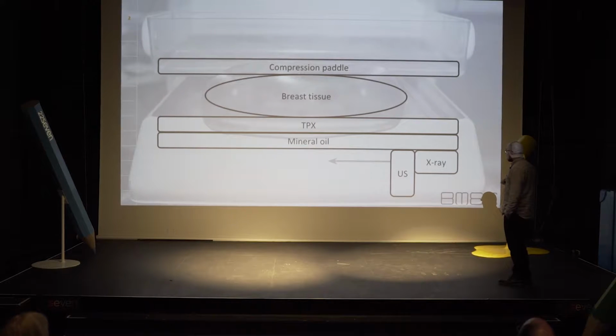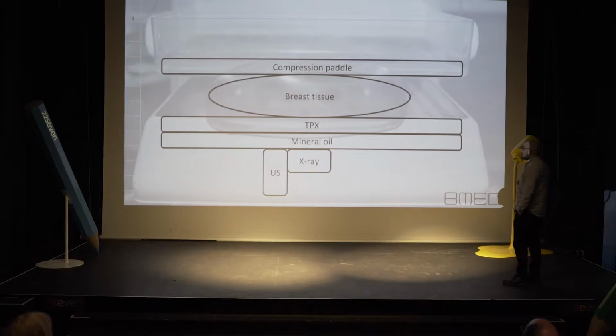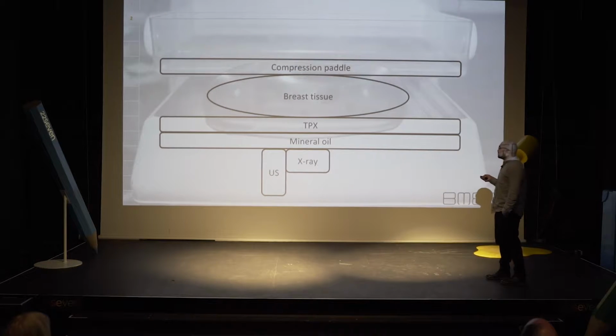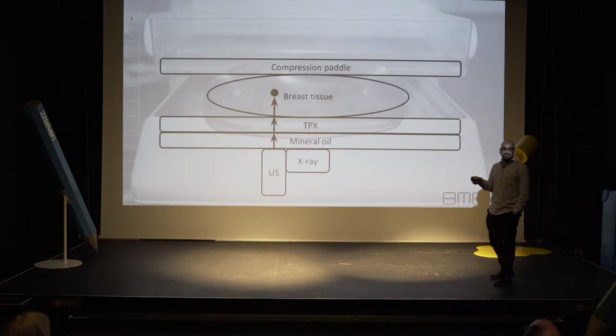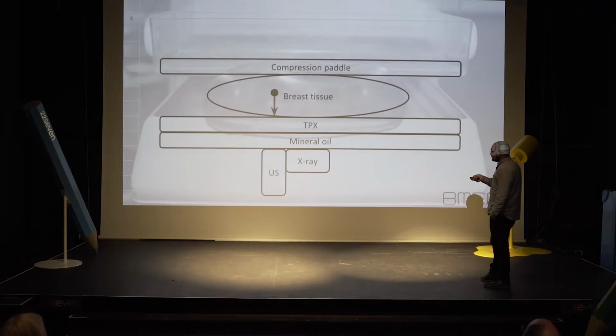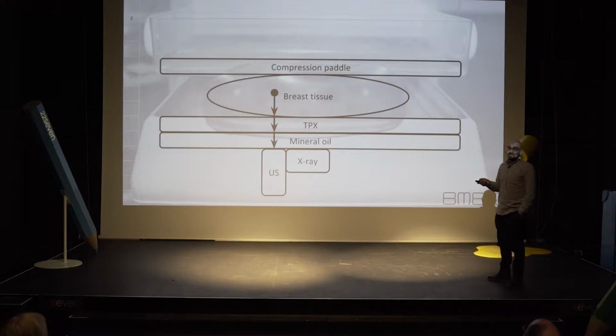So during a mammogram, the X-ray detector and the ultrasound probe move within the breast platform, and that's to acquire an image of the entire breast. The basic principle of ultrasound is that it generates sound waves. So here the ultrasound probe generates sound waves. They travel through the mineral oil, through the TPX, and into the breast. Once inside the breast, when the sound waves hit some internal breast structures, some of the sound waves get reflected back to the probe, which is then listening for the reflections. And the time between when the sound waves are sent to when they are received is used to create an ultrasound image.